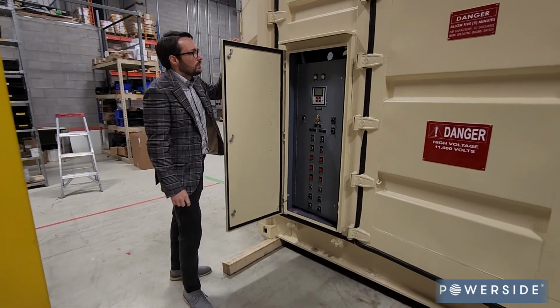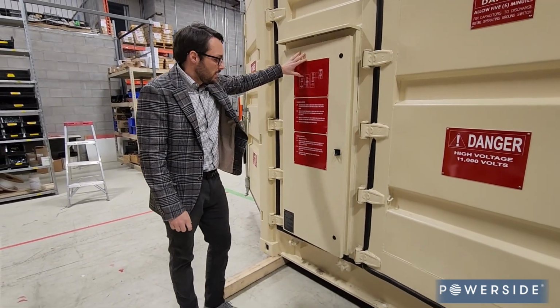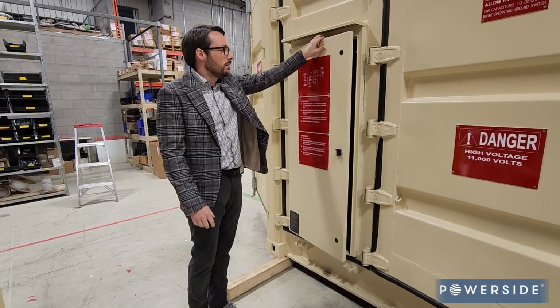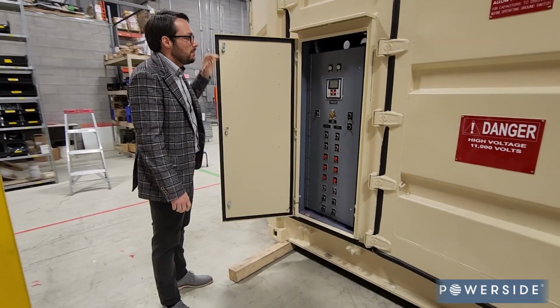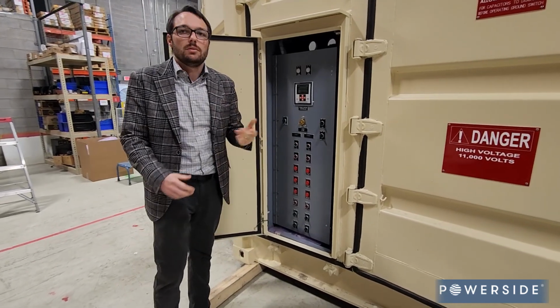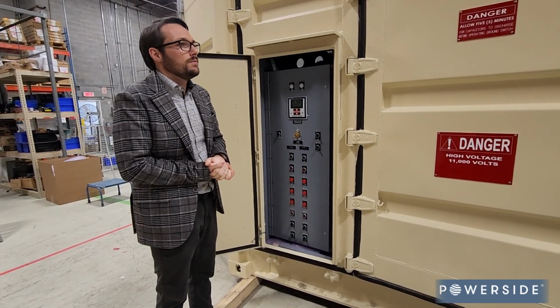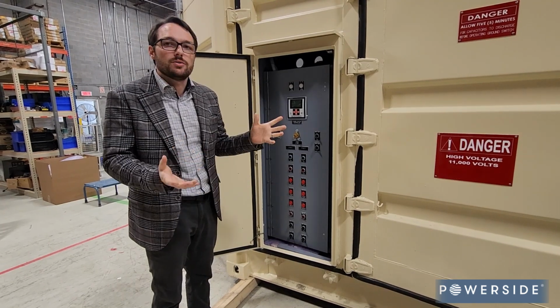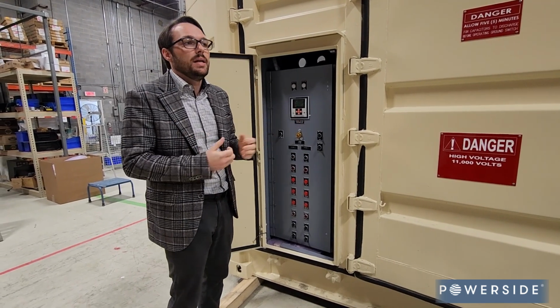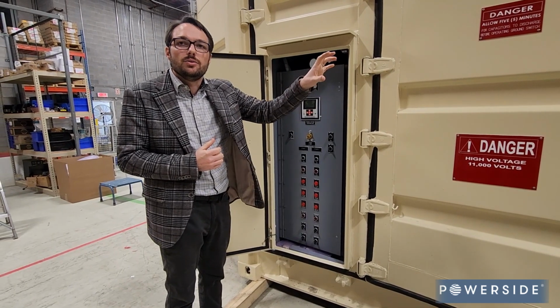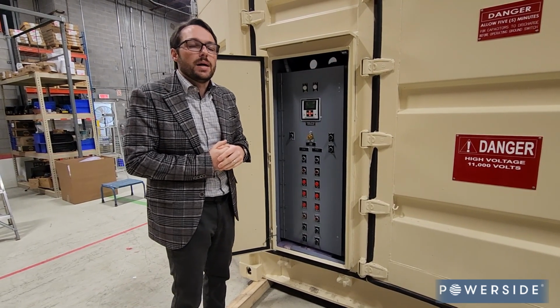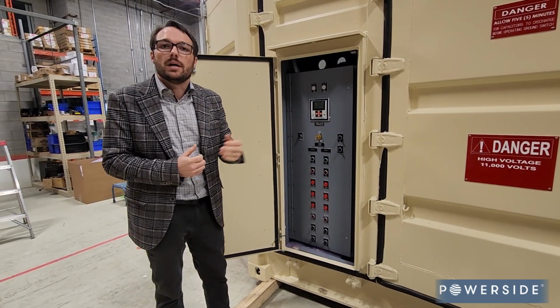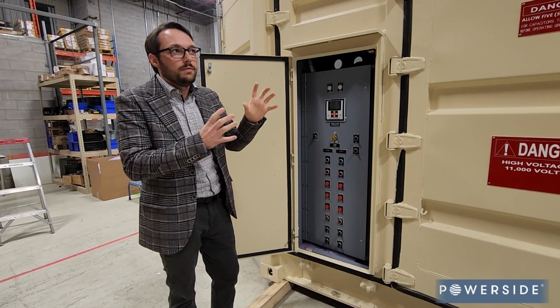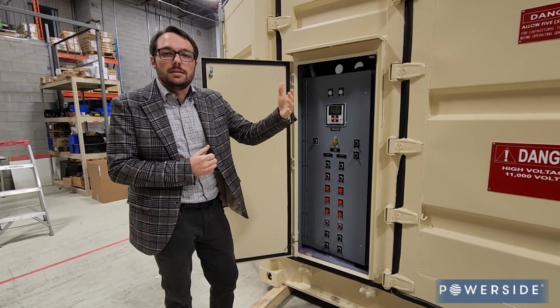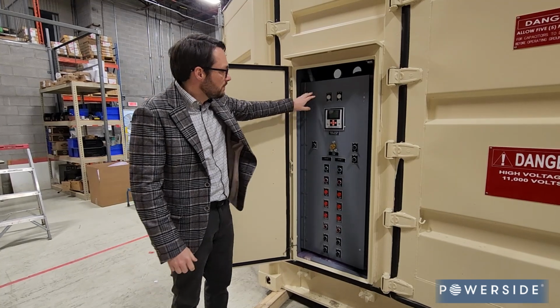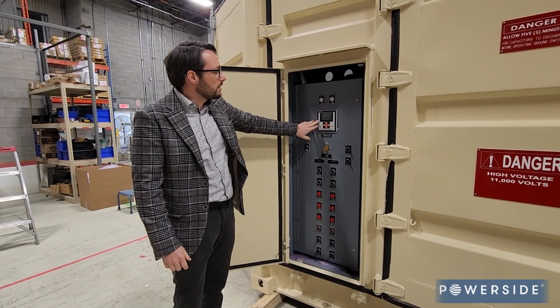So here we have our control enclosure, and this is built per the customer's requirements and specifications. Again, we're primarily using this in power factor control mode. The main function for this bank is to do power factor control, and we're trying to eliminate the risk of resonance by adding the detuning reactors in front of the capacitors. This was a requirement once we did a harmonic study and looked at the total of 5MVar that's required on the system. It needed to be a detuned system. So here we're using our power factor controller.